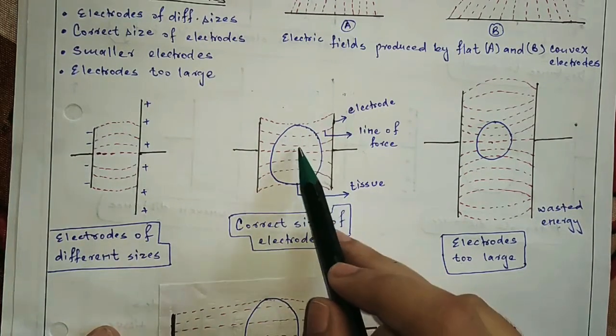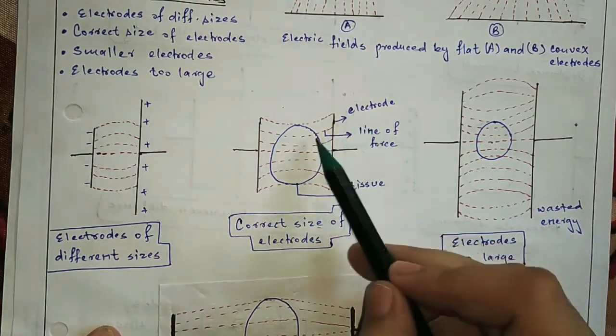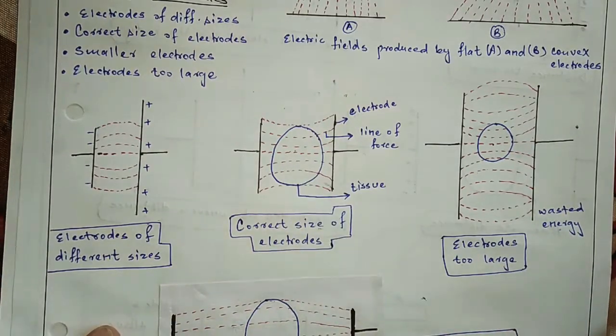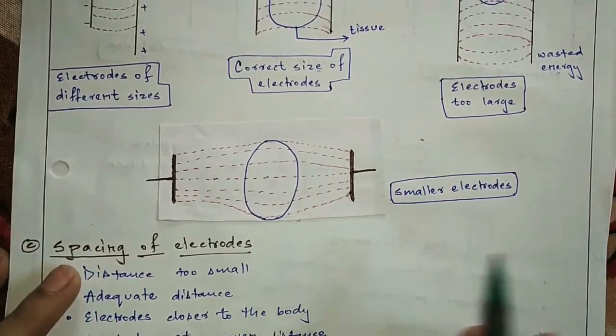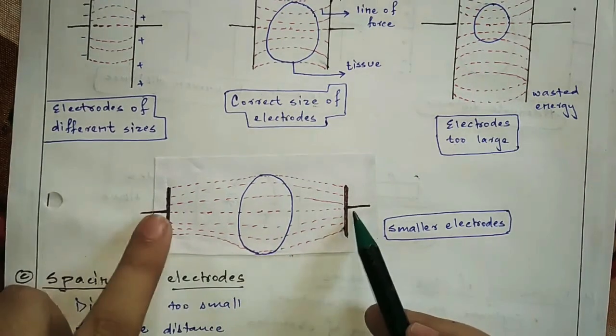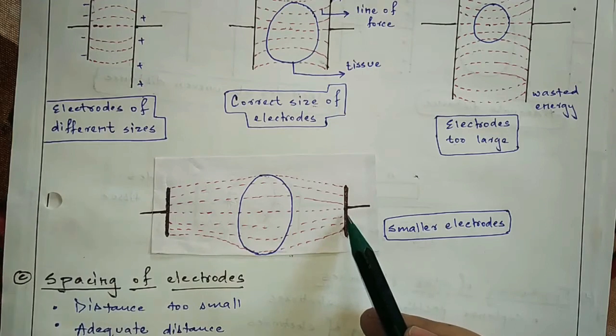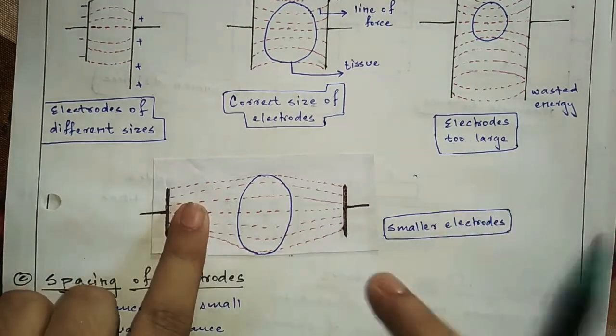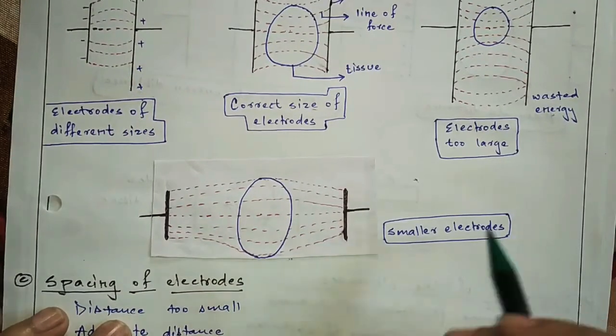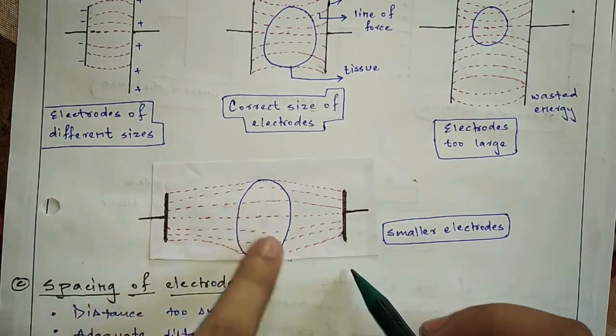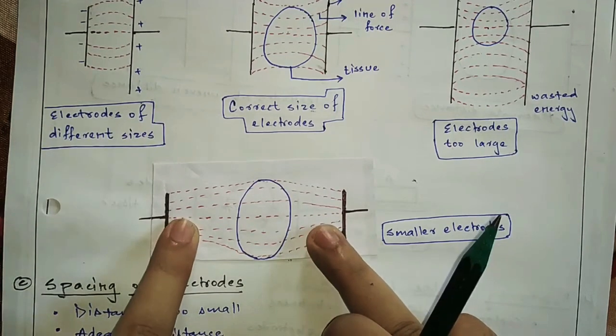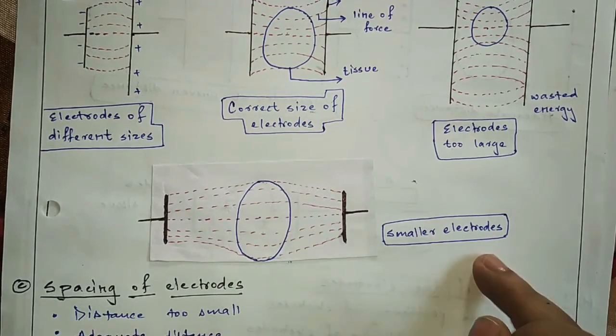The correct size of electrode is important — it should not be too large. If the electrode is smaller than the body part being treated, the concentration of the electric field will be more in the superficial part and less in the deep structure. As a result, deep heating will be insufficient. So the electrode should not be smaller than the body part.